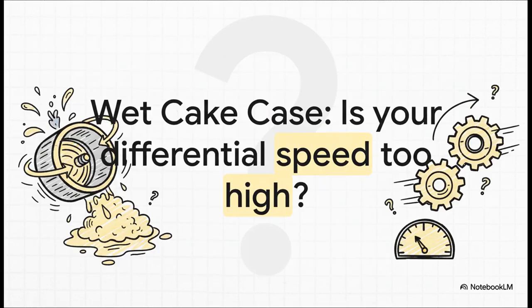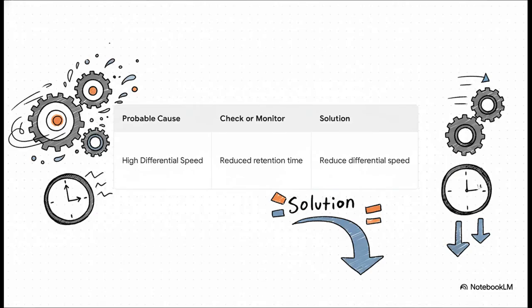So let's apply this to our wet cake problem. If your centrifuge is spitting out wet, sloppy cake, the very first question you should be asking yourself is about that differential speed. Could it be set too high? And here's why that matters. A high differential speed means that internal scroll is just pushing the solids out way too quickly. They simply don't get enough retention time under all those G-forces to properly dewater. The solution? You guessed it, reduce the differential speed, slow it down.